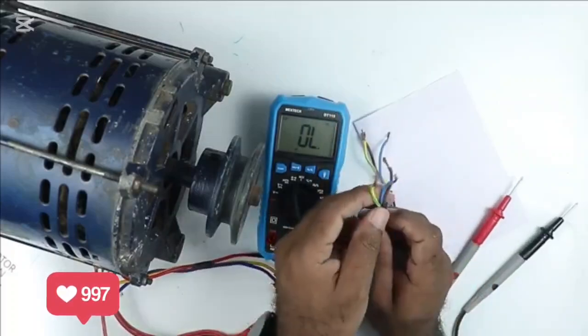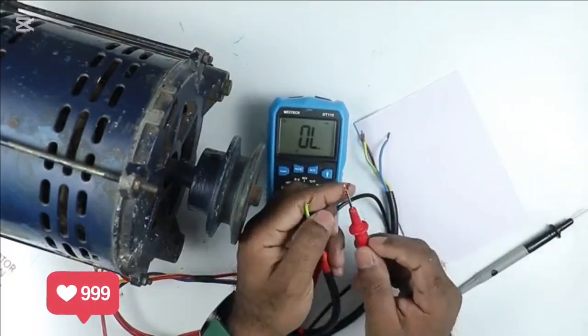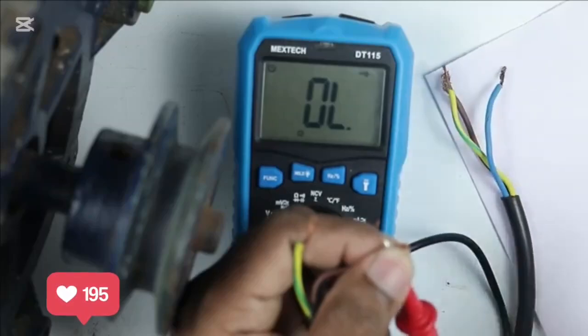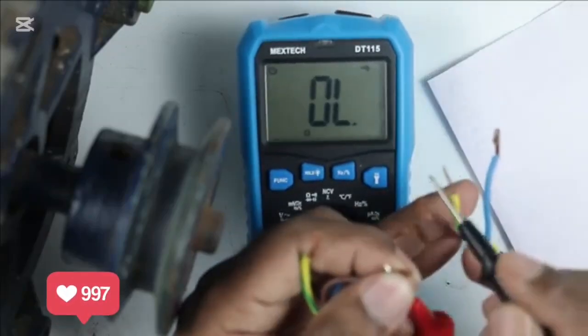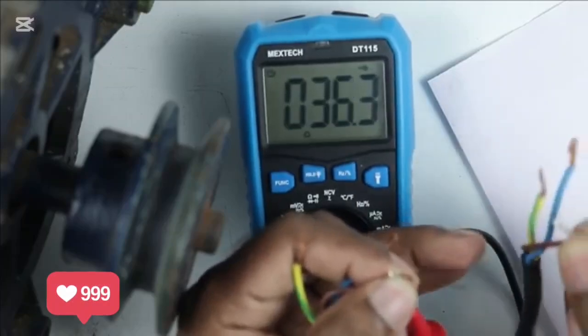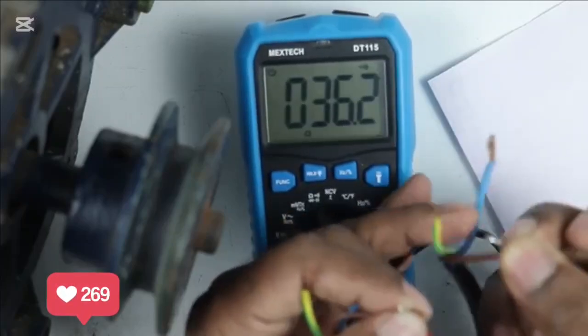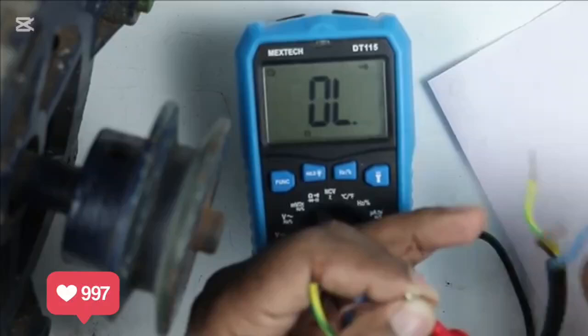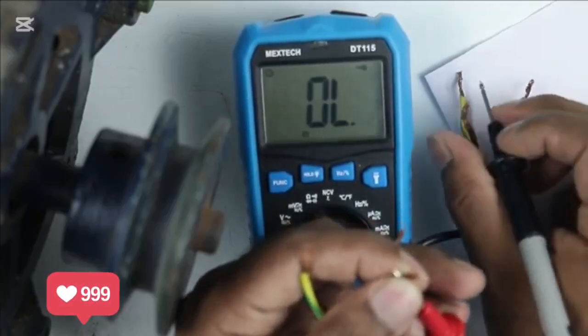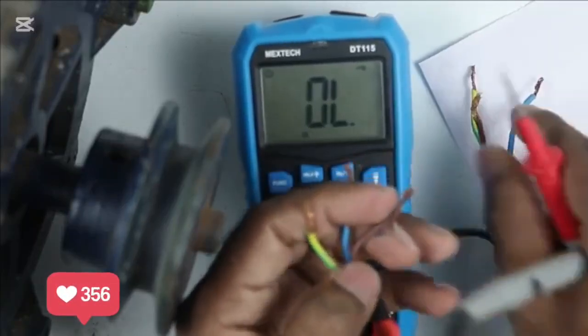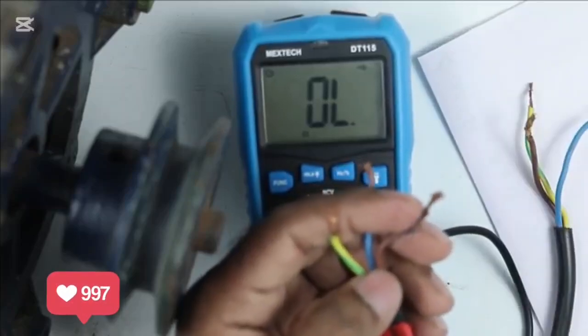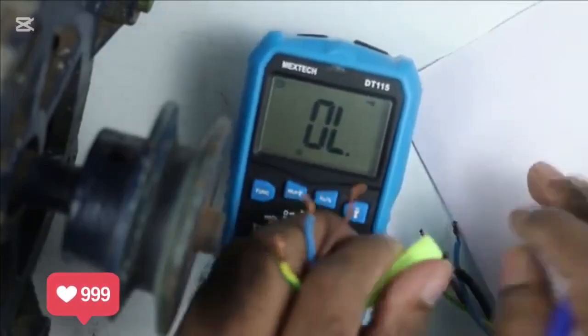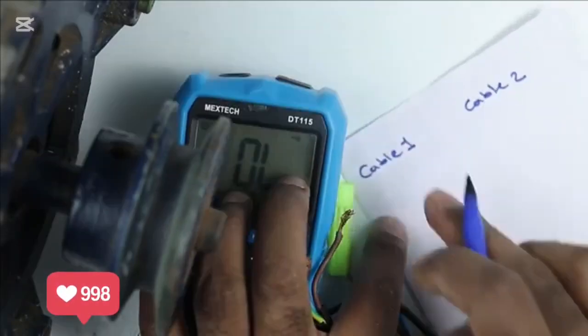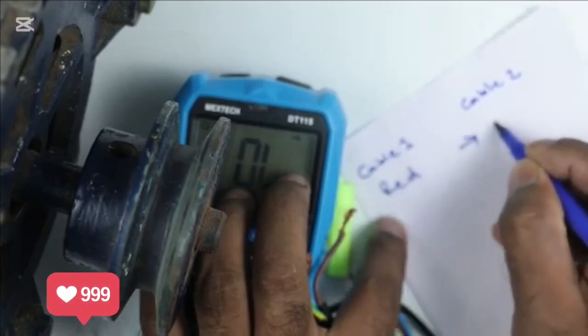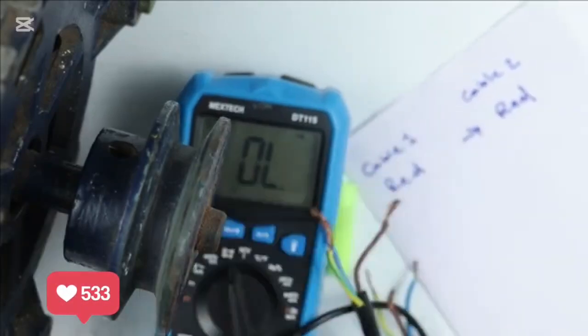In this first cable, connect one probe of the multimeter to any one of the wires. I connected the probe to the red wire. Now in the second cable, connect the other probe to the red wire. Here I am getting continuity. If I didn't get continuity here, I would connect the probe to another wire to check. We just have to confirm which wire this wire has continuity with. Here I am getting continuity of the red wire with the red wire, so I will make a note for identification. First I will write cable number 1 and cable number 2: the red wire of cable number 1 has continuity with the red wire of the other cable. Cable number 1 is the one with the red tape.